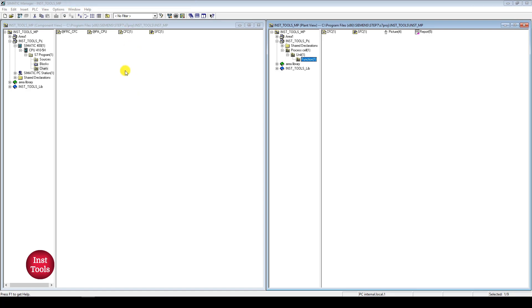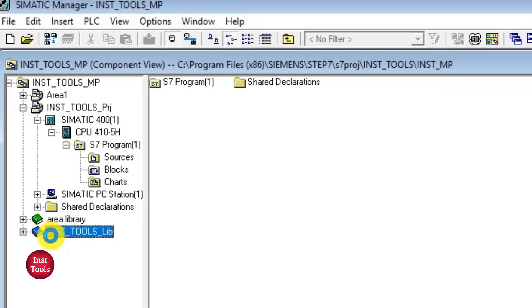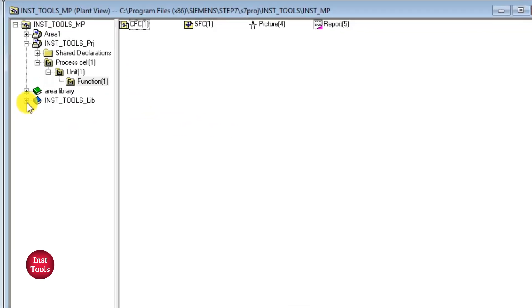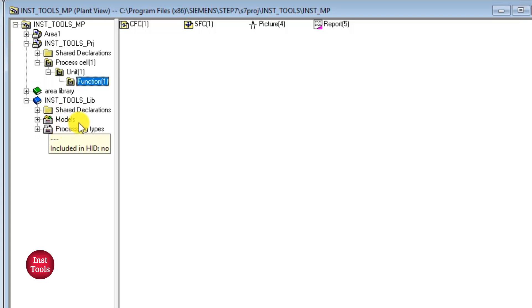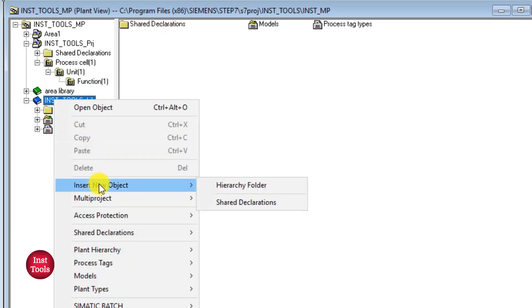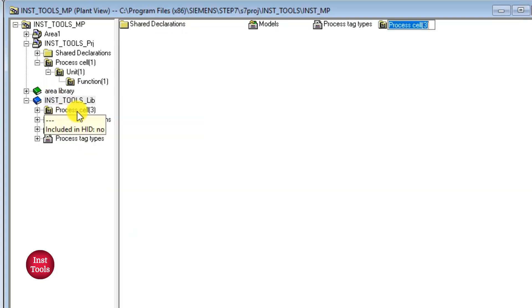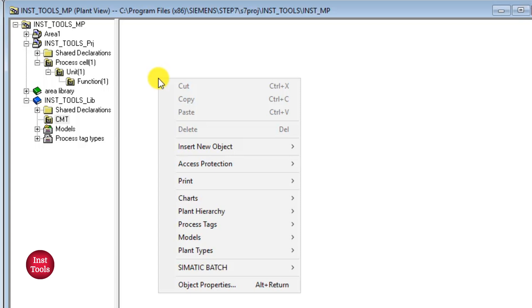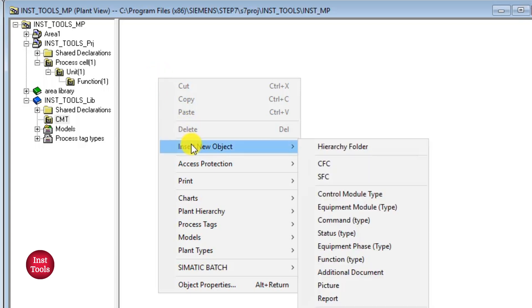We navigate to the master data library. We can navigate via component view or plant view — for ease, since we are working on logic, I prefer plant view. Inside the master data library I have three subfolders: models, process tag types, and shared declarations. I will create my own hierarchy folder inside the library, rename it to 'CMT', and on the right-side pane, right-click, insert new object — insert control module type, which is the CMT.